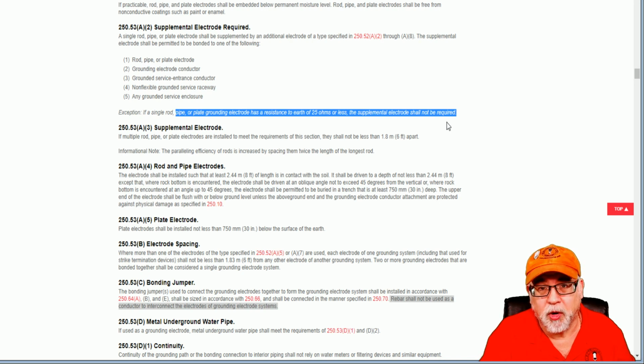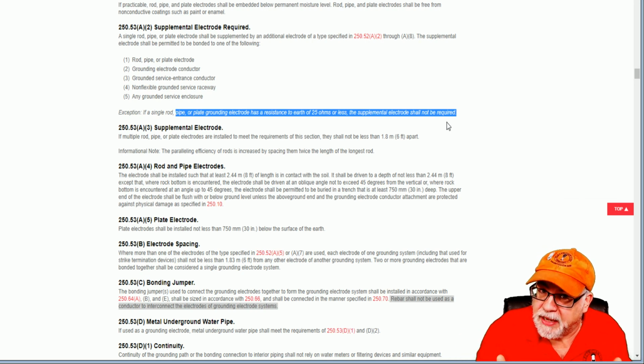You need a clamp-on ground resistance meter or a 3-point fall-of-potential setup to be able to do that. And usually, with the 3-point fall-of-potential, you have to have enough space to do it, okay? You have to space the probes out so far that go into the earth, and it can be very space restrictive.